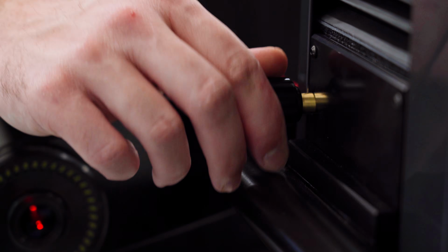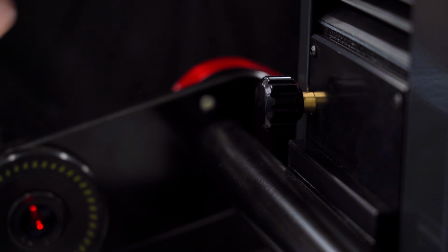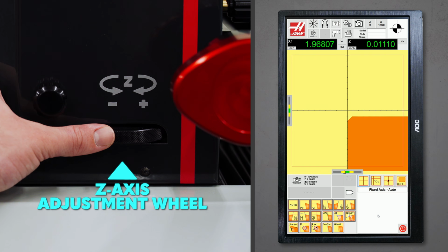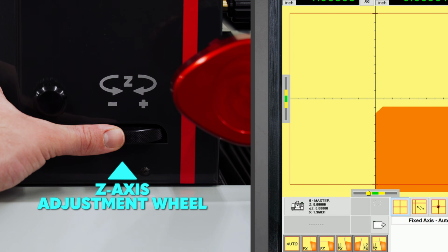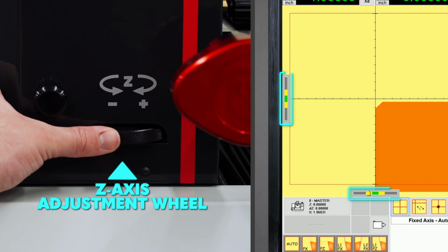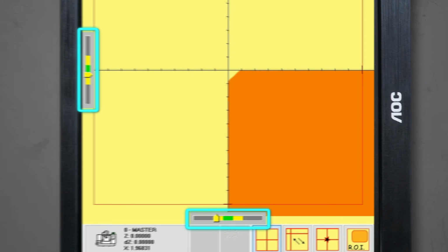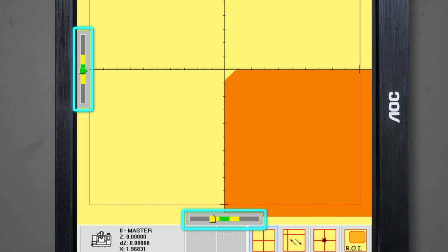Once that is done, tighten both the axis locks and use the adjustment wheels to move the crosshairs into position. While you're doing this, you'll notice that there are two arrows that move as you get closer to the edge of the X and Z axis. These arrows let you know how close the crosshairs are to intersecting with the edge of the axis, with an arrow in the green zone being the most accurate.